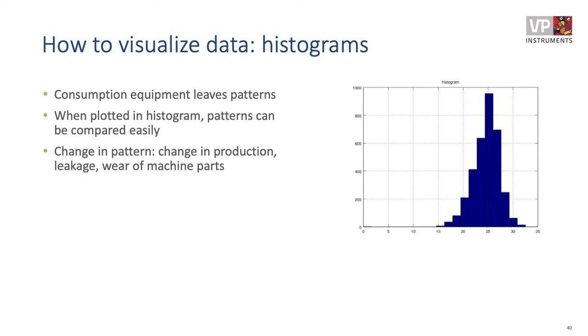Well, the simplest type, I would say, and also the best technology for compressed air, is still a thermal mass. And why is that? Because the measurement range of the flow meter is very large. So you can measure both very low consumption and high consumption with the same meter. There are also other technologies used, like, for example, vortex meters, differential pressure. And all these technologies have different features and benefits. Differential pressure and vortex based typically are used for more harsh environments. So they basically last longer in harsh environments. They can handle much higher temperature and water. So less maintenance.